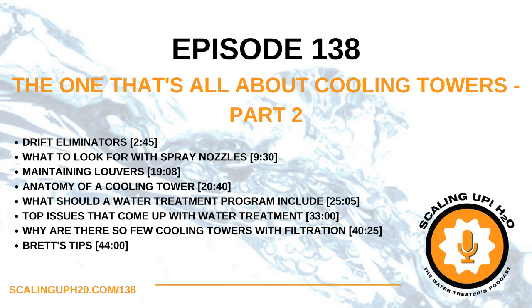What other tips do you have for us, Brett? I'd say the last one is these closed circuit coolers and evaporative condensers, when they have the spray pump out by the unit and the riser pipe, we call them integral sump. So all that recirculating water is right out by the unit, which means your water treatment has to be out by the unit too.